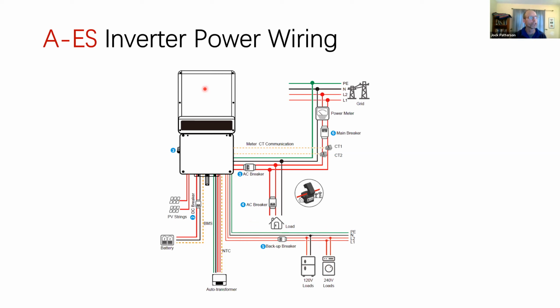So if this inverter was a 9600 watt inverter, we can always push out 9600 watts with the right battery. We can always push out 9600 watts to the backup circuit. But for the first minute, for up to 60 seconds, we'll push 20% higher than that. So we'll be doing something like 11.52 kilowatts for up to 60 seconds to make sure that all the loads start up.